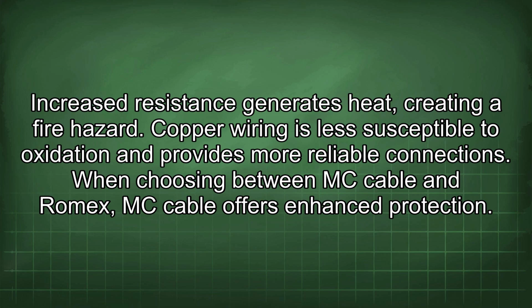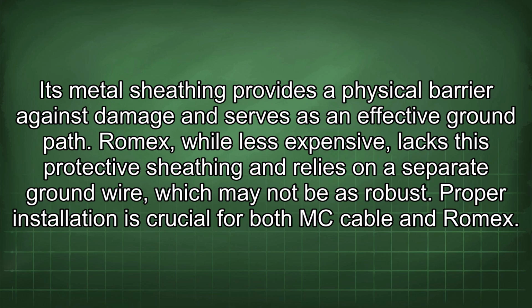When choosing between MC cable and Romex, MC cable offers enhanced protection. Its metal sheathing provides a physical barrier against damage and serves as an effective ground path. Romex, while less expensive, lacks this protective sheathing and relies on a separate ground wire, which may not be as robust. Proper installation is crucial for both MC cable and Romex.